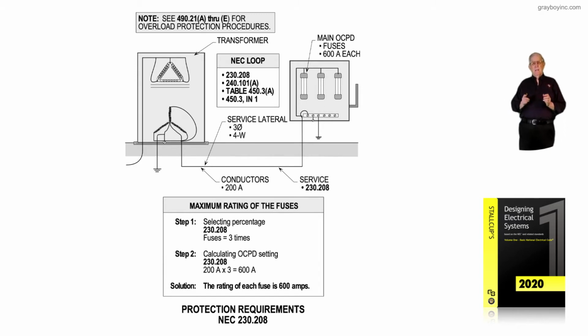Now, what this is pointing out is that for conductor protection, we are referred to Article 240, 240.100 and 240.101. But for services, our protection requirements are in 230.208. And if we're using fuses for protection for transformers or conductors, and the conductors are rated 200 amps, then in step 1, the boxed information for sizing the maximum rating of the fuses, it'd be 3 times the conductor ampacity. So a 200 amp conductor times 3, we could size those fuses at 600 amps.